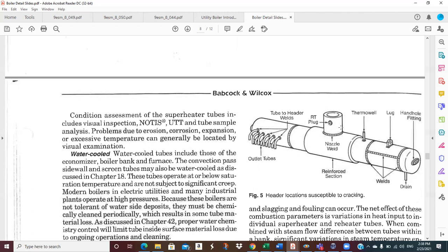Well, we have a header at the bottom of the boiler, so that big pipe from the drum falls down into this, that water spreads out, and it feeds all of these individual tubes that then line the furnace, and so that water flows. Either you can pump it, or it'll go by natural density differences, because you got water on the backside and you got water and steam on the front side. And then up at the top of the boiler, you have to have one of these where you collect it again and then put it into the steam drum. So we got headers all over the place.